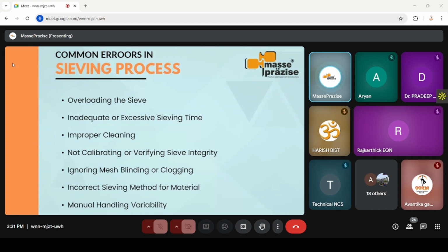Not calibrating or verifying sieve integrity. Using sieves without regular mesh verification or inspection may cause undetected mesh damage, which leads to inaccurate results. So we have to verify the test sieve before every use. A physical verification is very important for the test sieve before every process or before each use.